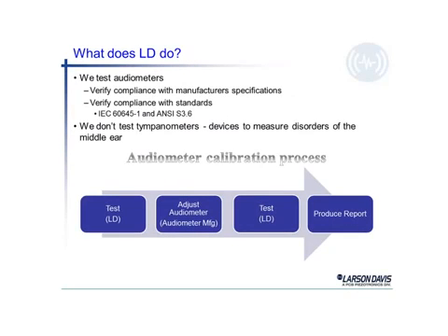What does LD do? We test audiometers. We verify the compliance with manufacturer specifications. We verify compliance with the industry standards. We do not test a device called a tympanometer. That's a special device used to measure disorders of the middle ear.